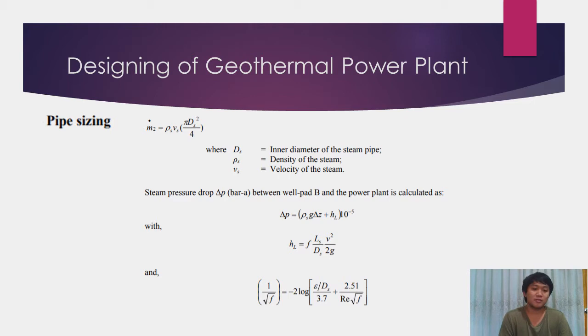Steam pressure drop delta P between well pad B and the power plant is calculated as delta P equals density times gravity times delta Z plus H sub L, head loss, all times 10 to the power of negative 5, with head loss equals to f times L sub S over D sub S times V squared over 2g, and 1 over square root of f equals negative 2 log of epsilon times D sub S over 3.7 plus 2.51 over Re, Reynolds number, square root of f.